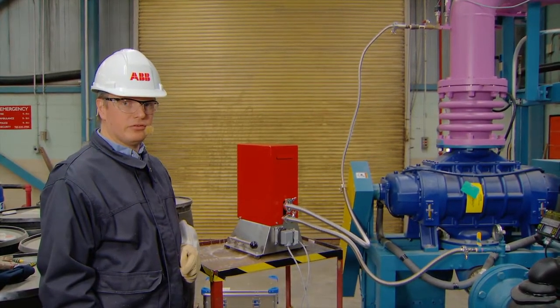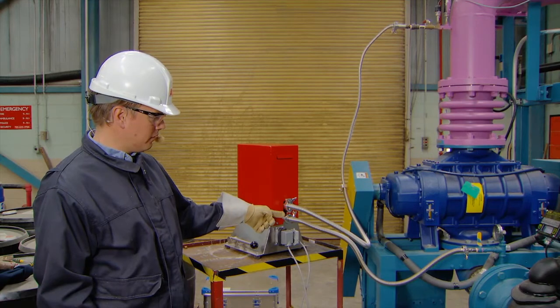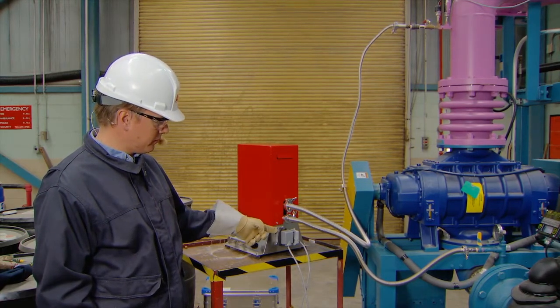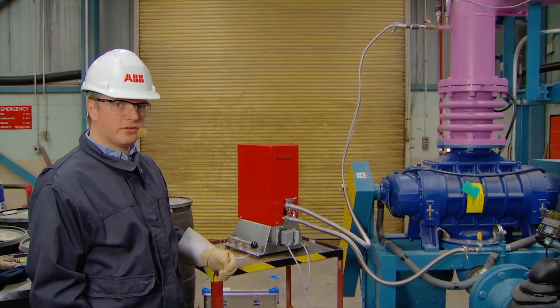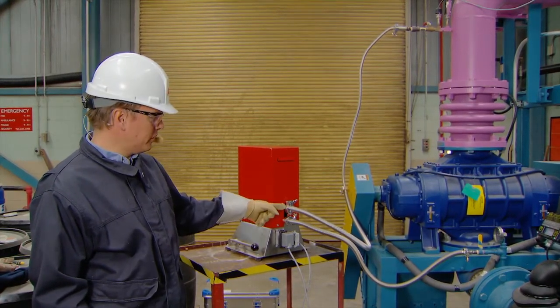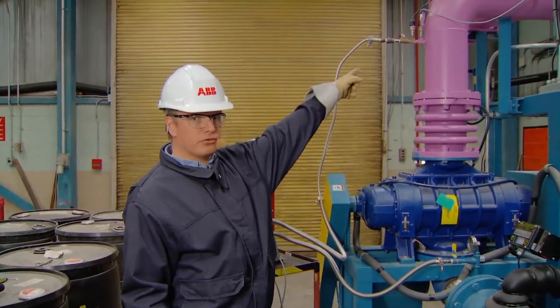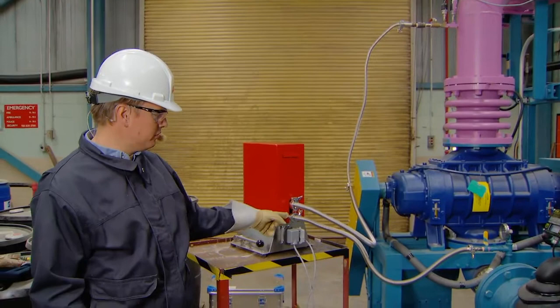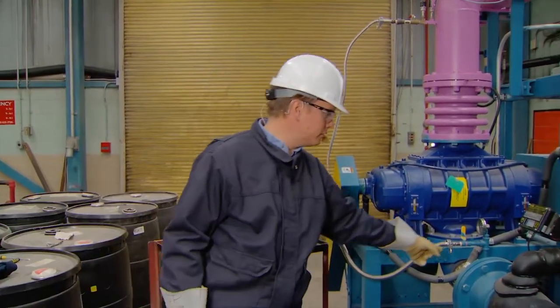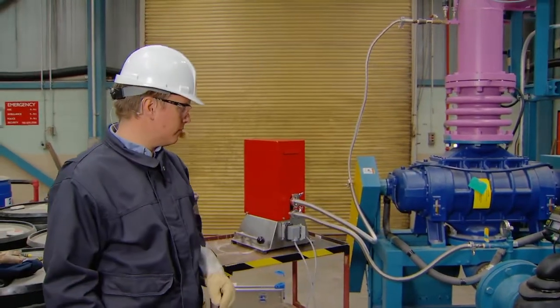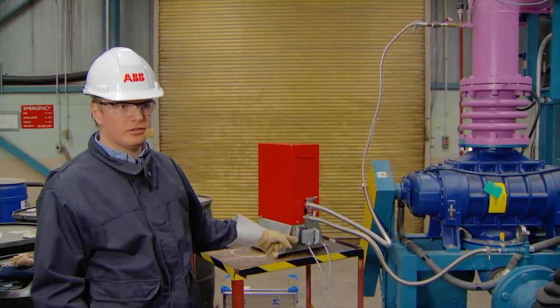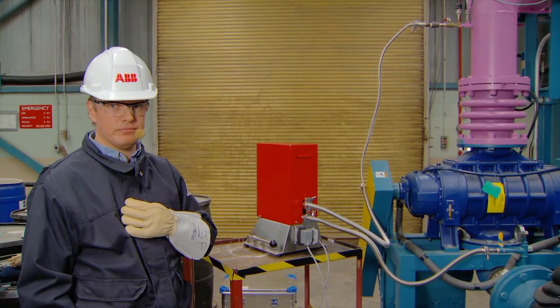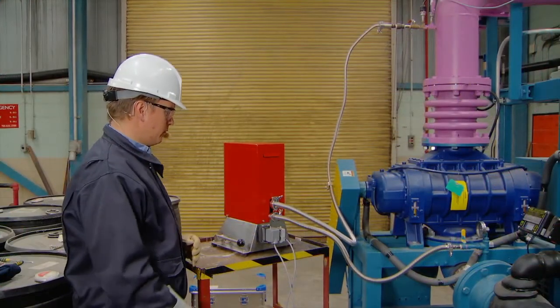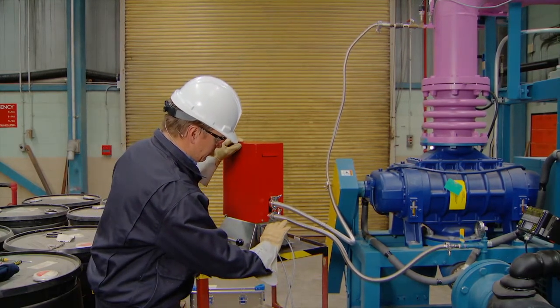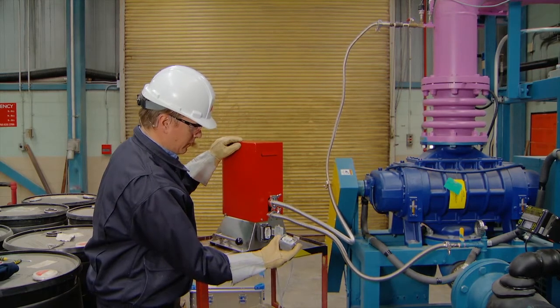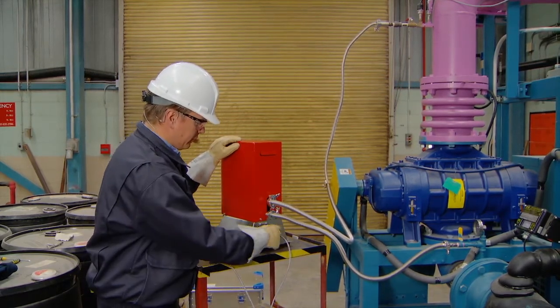On the back side of the VSAD 406 you have the vacuum connections and the electrical connections. The vacuum connections have to be connected over the root pump. The upper connection should be on the suction side of the root pump, and the lower connection should be on the pressure side of the root pump. The electrical connection goes directly to the control panel in the converter trailer. There are two electrical connections. One is for the magnetic valves and the motor, and the second one is for the pressure sensor inside the VSAD 406.